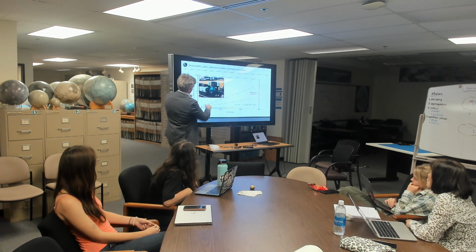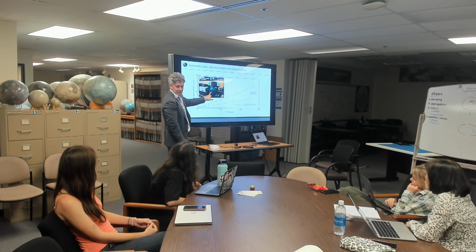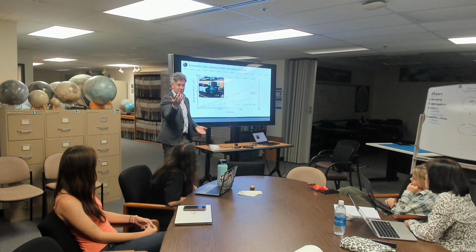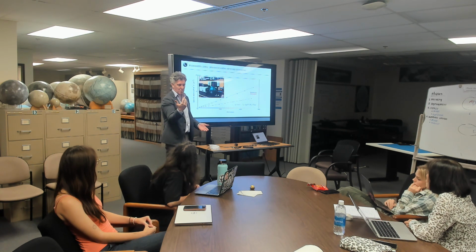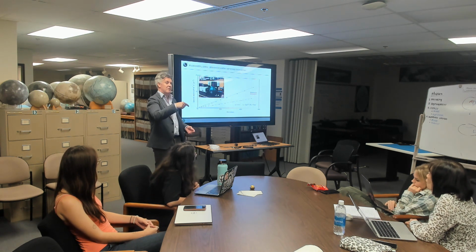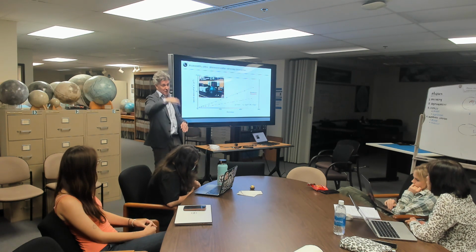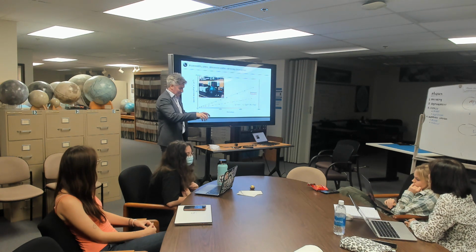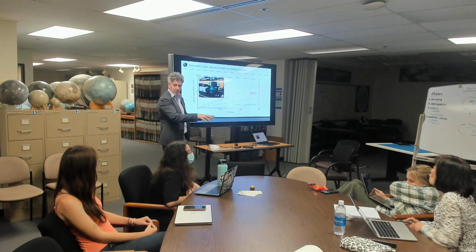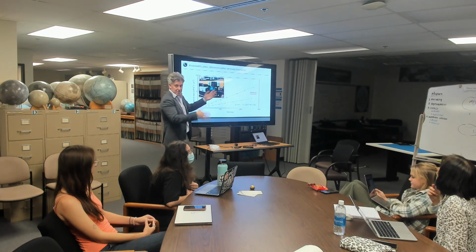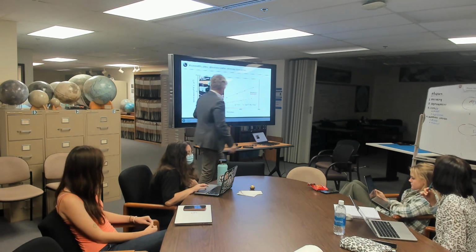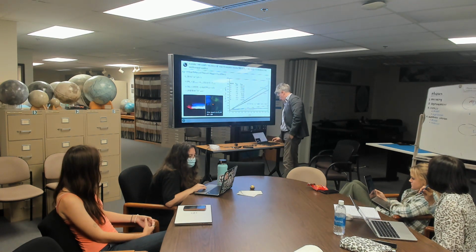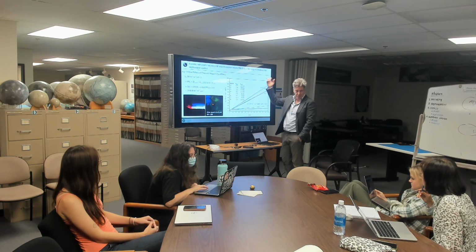And then I turn the knob slightly to the left, and I admit more light into the sphere. And then I say, well, now what's the DN? And the DN should go up, because more photons are arriving at the focal plane array. That means more photoelectrons are being generated. That means the DN should go up. And I put another plot, and then I just keep doing that. I keep admitting more and more light into the sphere, known amounts of light, and I keep recording the DN that the instrument's giving me. And at the end of it, I go from here to here, and I fit a straight line, and that allows me to generate a calibration coefficient for that wavelength.